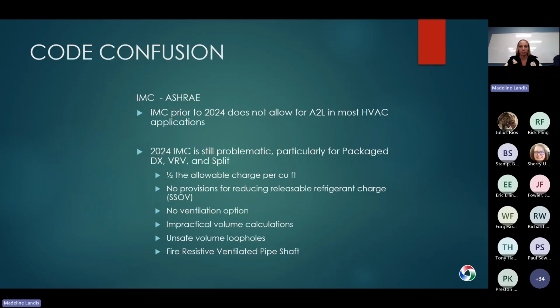What I will talk about is the confusion that's out there because the actual code adopted by jurisdictions involves the International Mechanical Code. And the International Mechanical Code prior to the 2024, at the best you could say, doesn't address A2Ls in most HVAC DX type applications. And I would make the argument that it really doesn't even allow it in most applications. So that's why we've been talking ASHRAE.